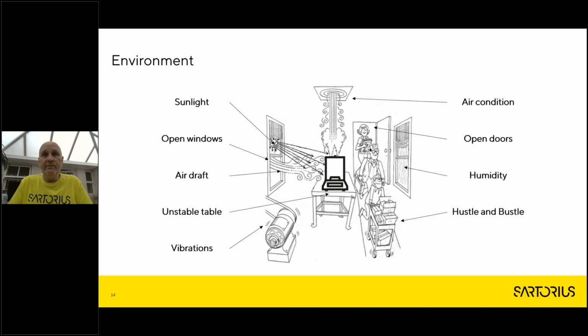Do we have a good table, or do we have a good bench or a weighing stone? Or do we have an unstable table? Is that table located in the center of the laboratory? It's better to be located at the side of the laboratory or against a wall for more support. Do we have any vibrations near the balance, or a piece of equipment on the same table as the balance generating vibrations? Do we have air conditioning in the laboratory? Is it over the top of the balance?